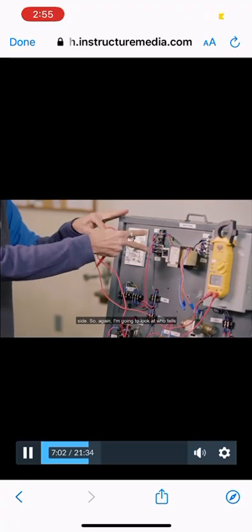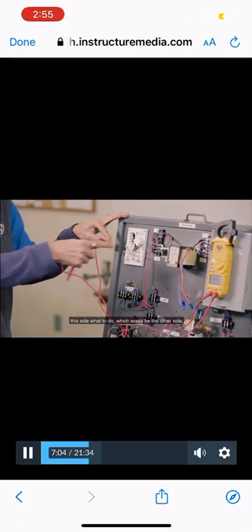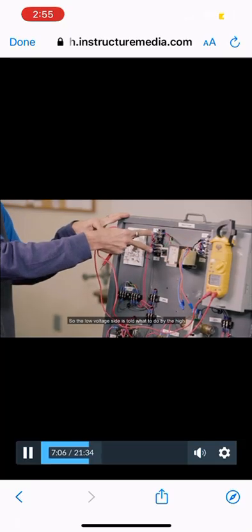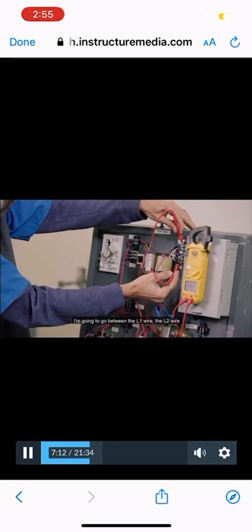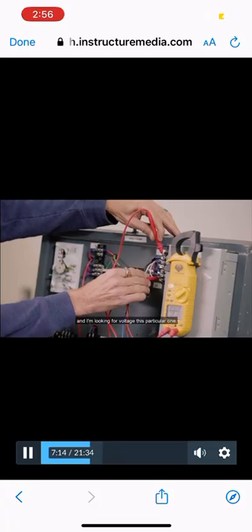So my next step would be confirming that my transformer is actually sending some power out. So I'm going to look, and I don't have anything on this side. So again, I'm going to look at who tells this side what to do, which would be the other side. So the low voltage side is told what to do by the high voltage side. So I'm going to take my meter lead. I'm going to go between the L1 wire, the L2 wire, and I'm looking for voltage.